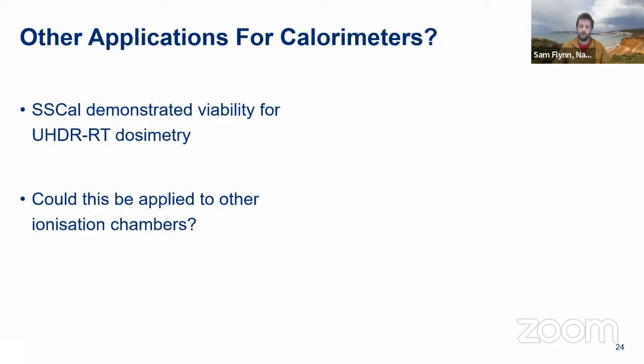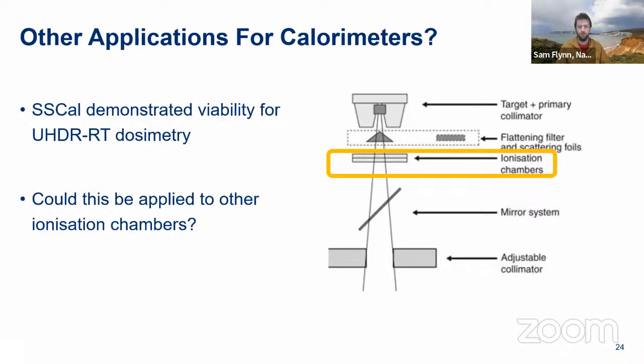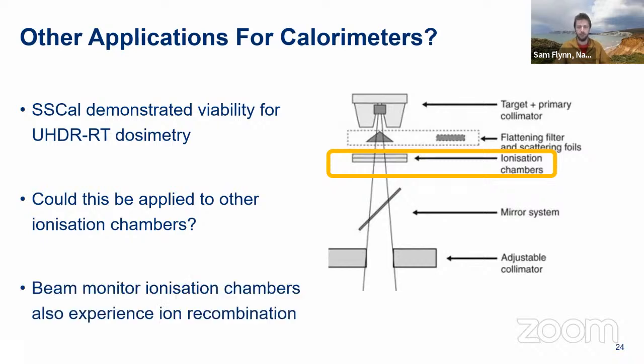The focus of the secondary standard calorimeter is on reference chambers, which are the workhorse of modern radiotherapy. But they aren't the only ionization chamber within the medical physics ecosystem. The other one being monitor chambers that are part of a dose delivery system. And we know that they experience the same ion recombination effects and uncertainties that need correcting for. So how do we put an ionization chamber into a beam delivery system? What changes are needed to make it fit?